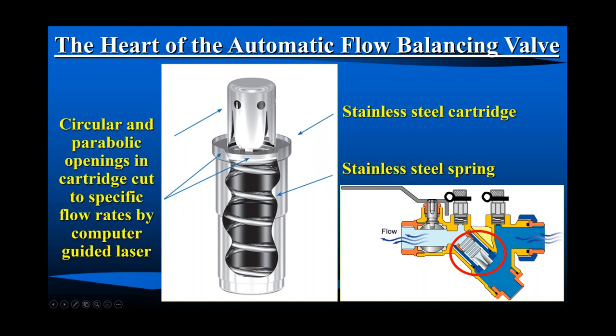So there are two different shapes, two different cuts from the factory that stick out into the water stream, a parabolic shape and a circular shape. And between these two openings, as it goes in and out of this cartridge, of course, this is the variable part. If it were to bottom out, if you will, the circular openings still remain in the water stream, providing a path for water to flow through the device. We do not want to deadhead any pumps. And this is a cap. So if you wanted to take it out, you certainly could and put it back in. There's another reason for that. We'll talk about that next. So that's what's on the inside of an automatic flow balancing valve. Most of the manufacturers make it of stainless steel. There are some folks making it out of plastic as well.